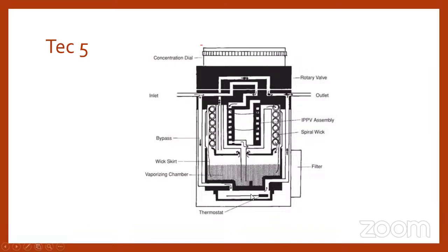The bimetallic thermostat to control the temperature will be at the bottom, and it has a series of wicks to increase the surface area of absorption. So the inlet will be divided into two: one to the bypass channel, and the second to the vaporizing channel. The bypass will go in this pathway. It will go to the thermostat valve, so the temperature regulates the flow, and temperature will remain constant. Whereas the gas that enters the vaporizing chamber will pass through this IPPV assembly. So the pressure will remain the same, and the vapor present in the liquid agent will come out and mix with the part of fresh gas that enters the vaporizer, and both of them will mix here in the outlet, and the amount will be delivered to the patient. It has a rotary valve concentration dial, so we can adjust the concentration we want to deliver to the patient.